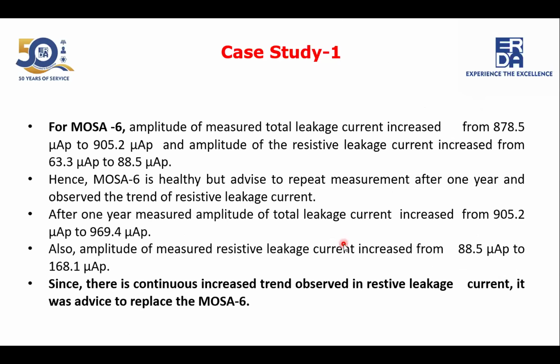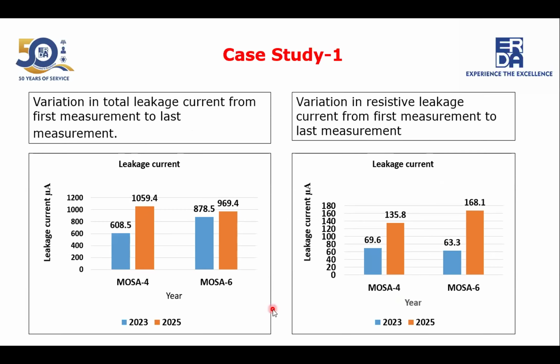Similarly, on MOSA 6, after 1 year the amplitude of the total leakage current increased from 900 to 969, and the resistive current increased from 88 microampere to 168 microampere. Since there was a continuous increasing trend observed in the resistive leakage current over 2 years, it was advised to replace the surge arrester, otherwise it may blast during an over-voltage condition.